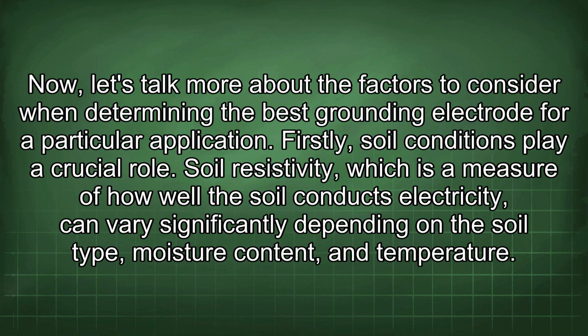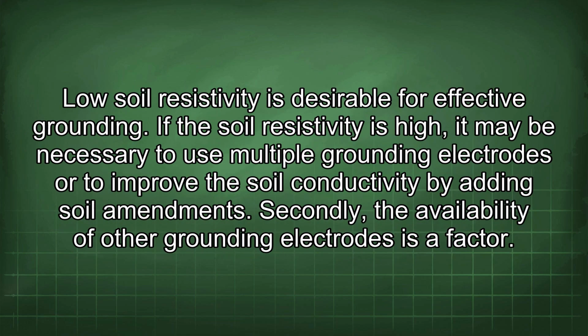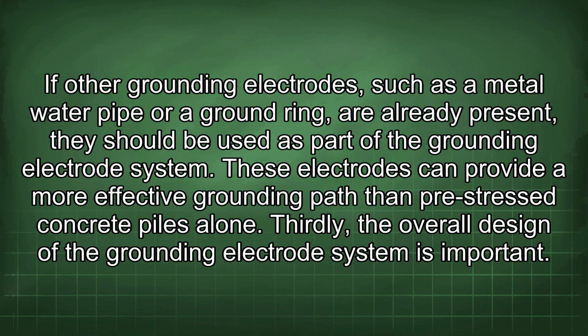Now, let's talk more about the factors to consider when determining the best grounding electrode for a particular application. Firstly, soil conditions play a crucial role. Soil resistivity, which is a measure of how well the soil conducts electricity, can vary significantly depending on the soil type, moisture content, and temperature. Low soil resistivity is desirable for effective grounding. If the soil resistivity is high, it may be necessary to use multiple grounding electrodes or to improve the soil conductivity by adding soil amendments. Secondly, the availability of other grounding electrodes is a factor. If other grounding electrodes, such as a metal water pipe or a ground ring, are already present, they should be used as part of the grounding electrode system.